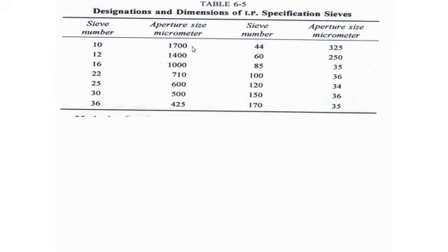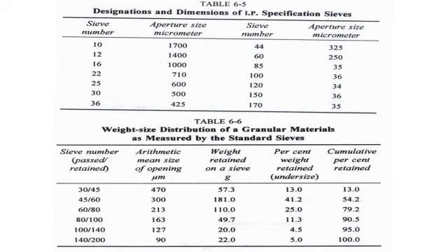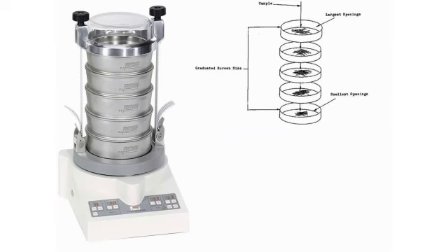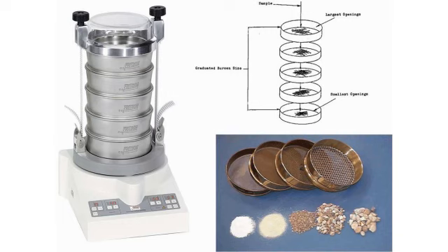The particles are considered to be retained on the sieve with the mesh aperture corresponding to the sieve diameter. The size is estimated as per given in the pharmacopoeia. As per the pharmacopoeia, sieve number 10 has aperture size 1700 micrometers. These are the numbers and this is the weight distribution. Whenever it will pass through the sieve we are going to have the weight distribution as per the pharmacopoeia. Let's see how the sieves are arranged. They are generally done in stacking method. The coarser sieve is at the top and the finer sieve is at the bottom.